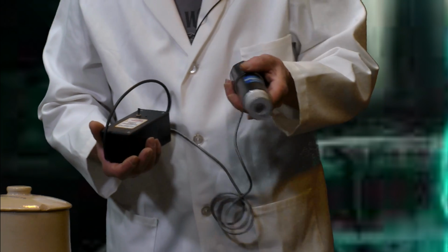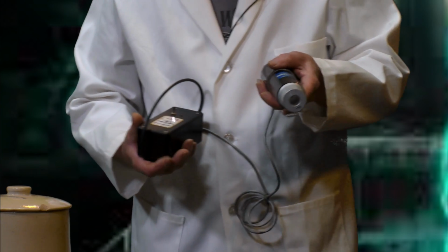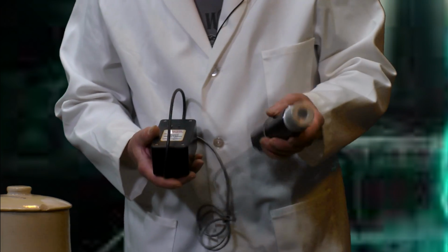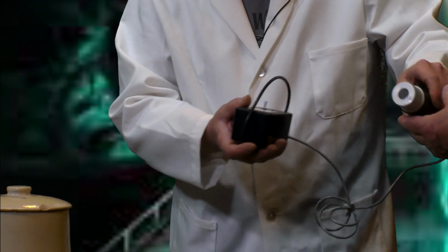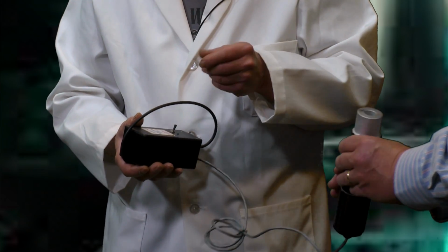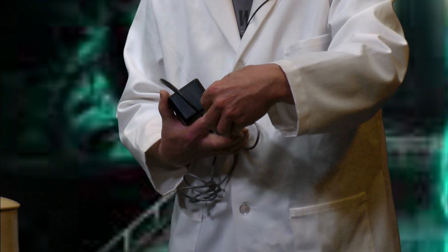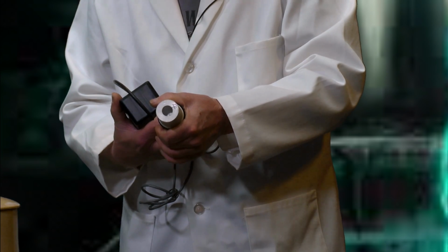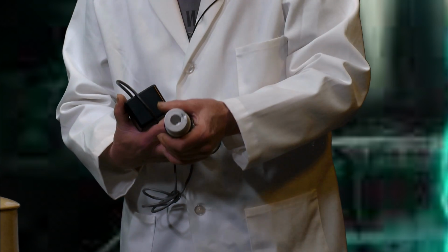Hence prospecting for a mine. It gets you in the general direction, and then when you get close enough, you'd have to stop using this and start using that. But the way a scintillator works, I'll try to make this as simple as possible. They take a crystal, for example, of sodium iodide, and they put it on the end of a special tube called a photomultiplier tube. Then they wrap everything in black tape and put it in a light-tight enclosure.